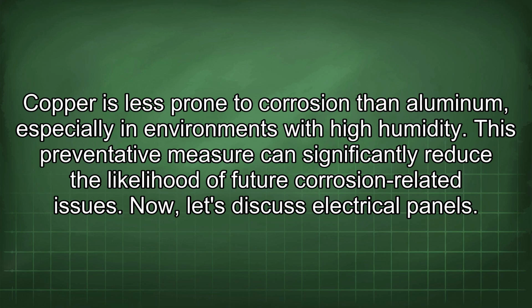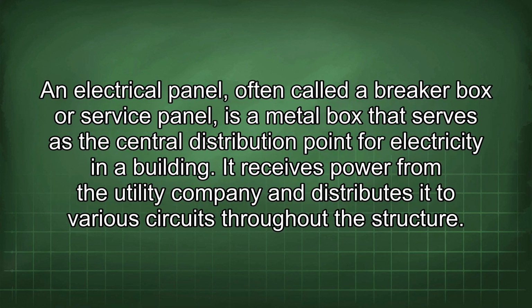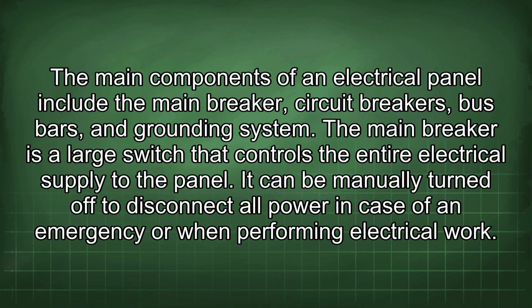Now let's discuss electrical panels. An electrical panel, often called a breaker box or service panel, is a metal box that serves as the central distribution point for electricity in a building. It receives power from the utility company and distributes it to various circuits throughout the structure. The main components of an electrical panel include the main breaker, circuit breakers, bus bars, and grounding system.